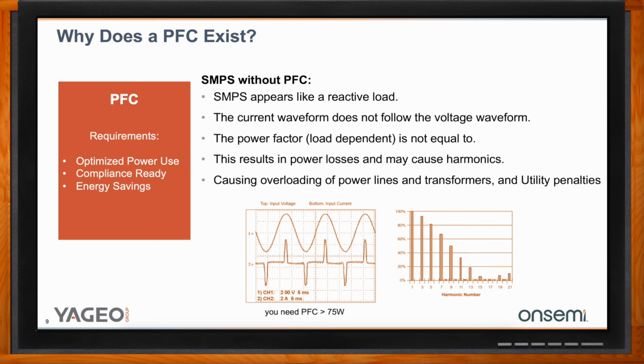The second point is load requirements. Many modern devices use switching power supplies for efficiency, which are by definition not linear loads. Those loads draw current in sharp pulses, rather than smooth sinusoidal waveforms, distorting the current waveform. This distortion introduces harmonics, which further reduce the power factor and cause additional losses and interference in the power system.